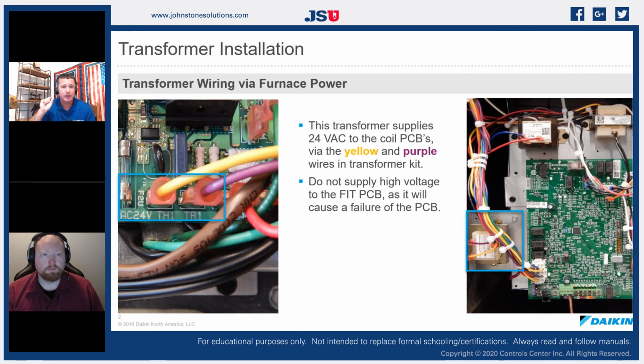So anytime we are installing a separate transformer on our communicating system, it is required that we ground it properly. Because what if it's just a zone control panel? If this is a Daikin Fit, it's using an EWC UT3000 zone control. It's the only one that works with the Daikin communicating systems, and it has its own separate transformer that needs to be installed in the furnace.